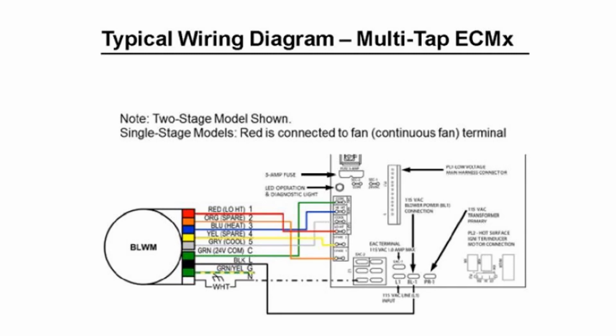It looks a lot like the old PSC motors that had taps where you could change the speeds. In this particular case, you have red, which is your low heat speed. Orange is a spare that you could swap to change the speed for low heat. Blue is your heat mode. Yellow is a spare that you could change. Gray is for cooling. And green is your 24 volt common.